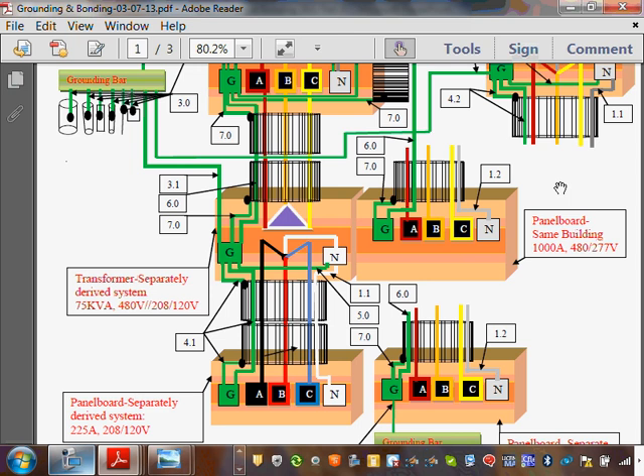Okay, so the first thing I want to size, guys, is, so we size, let's go, now coming to the transformer, you have to bring, can you guys see number 6.0? 6.0, that's an equipment grounding conductor to ground the transformer. You still have to pull an equipment grounding conductor to ground the transformer. And also you still have to bond the conduit, if it's metallic, the metallic conduit to the enclosure of the transformer. Bonding bushing. Again, 6.0 and 7.0, the equipment grounding conductor and the equipment bonding jumper load side can't be the same wire.